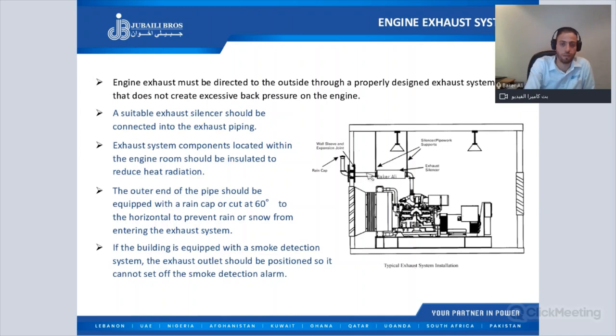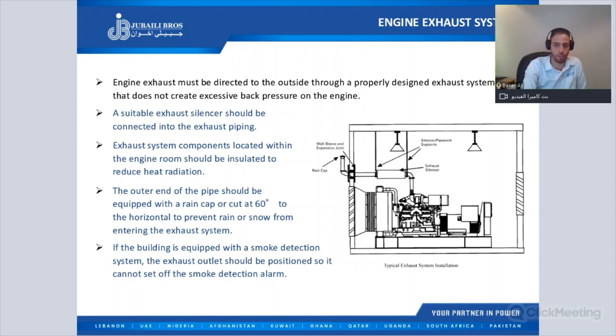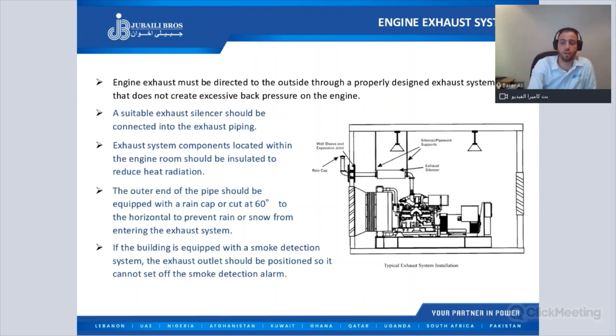If the building is equipped with a smoke detection system, the exhaust outlet should be positioned so it cannot set off the smoke detection alarm. If the generator is located inside a building, we have to extend the exhaust pipe to outside the building, especially if there is a smoke detection system, because when the generator runs, the smoke detection system will operate automatically.